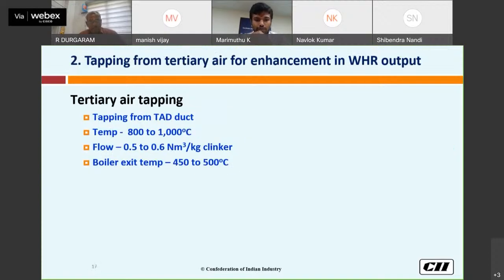Then the second one is the area to explore: tapping from tertiary air for enhancement in WHRS output. The tertiary air, which is at a temperature of around 800 to 1000 degrees, is what we give to the calciner. The flow we get is around 0.5 to 0.6 Nm³ per kg, and after giving it to the boiler, the boiler exit temperature is 450 to 500 degrees centigrade. This is based on a case study from one plant.